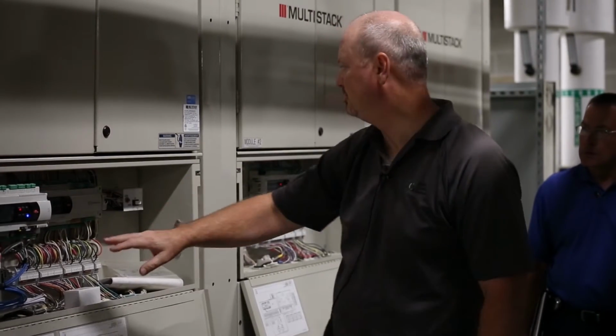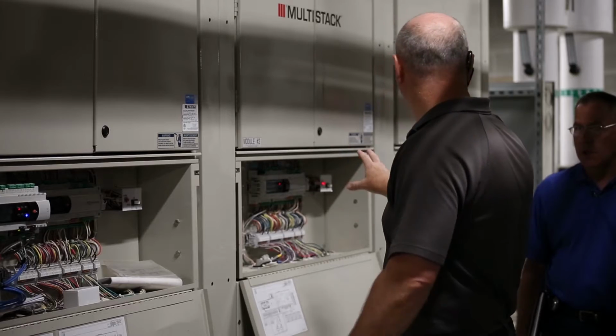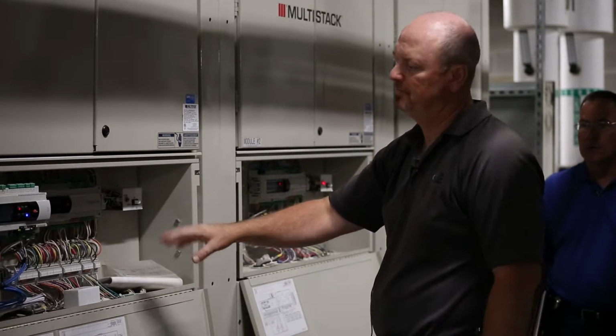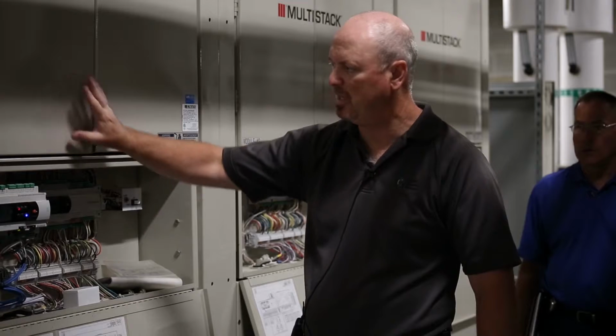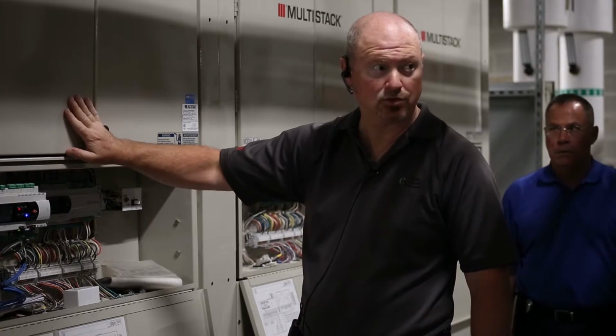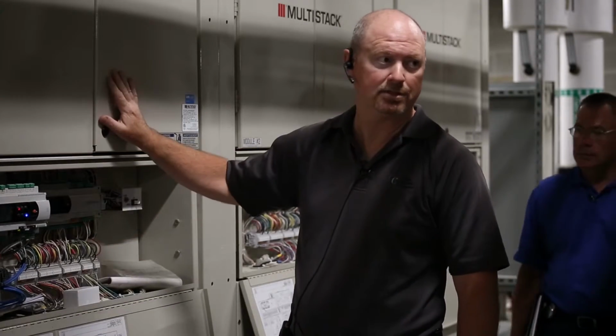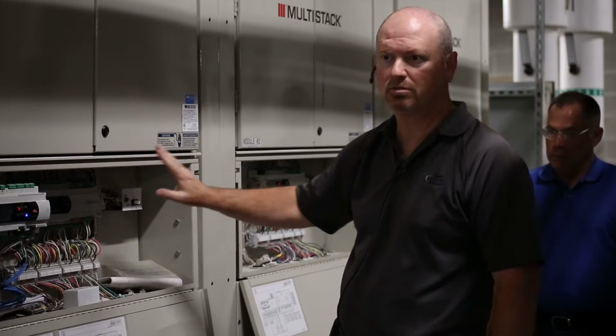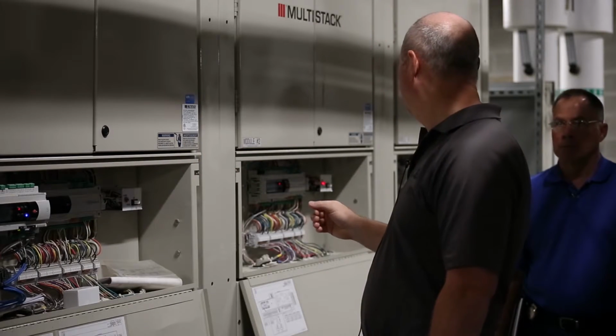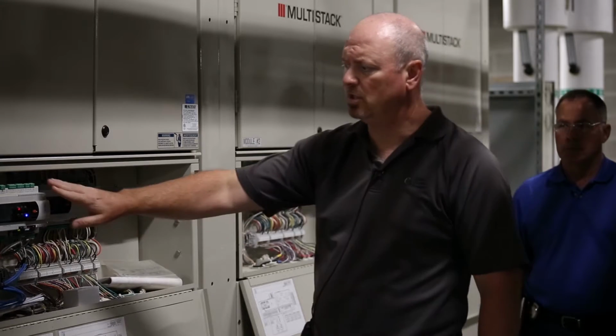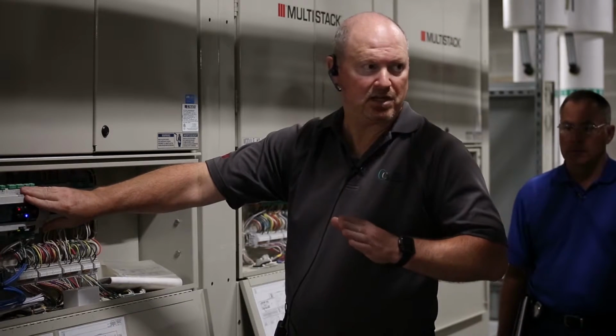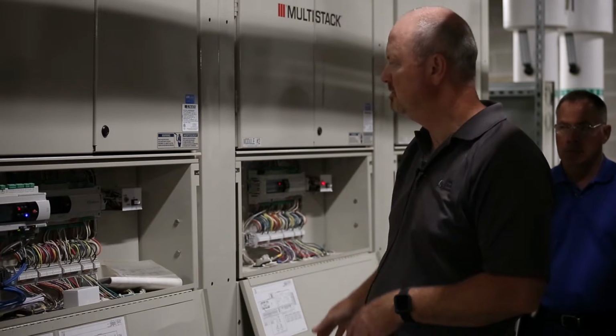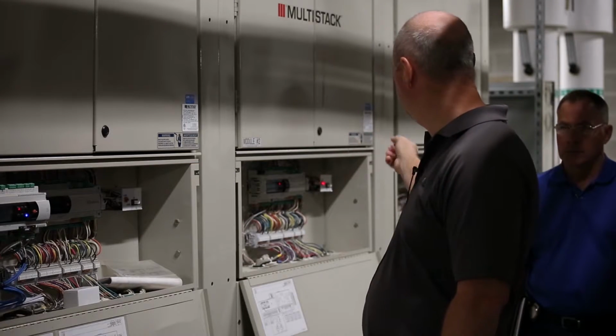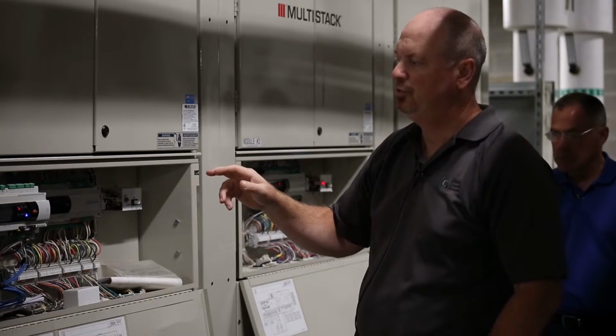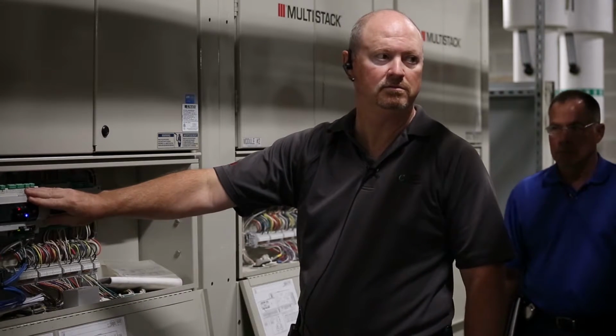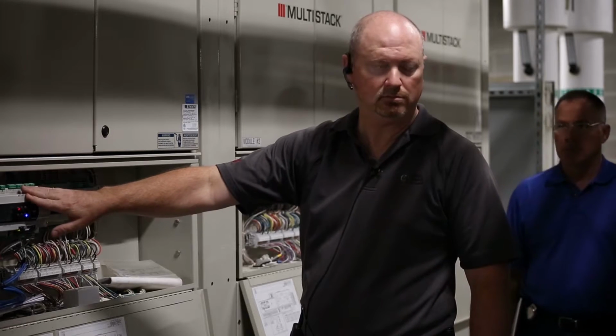This is your master, and these are all chiller module controllers. Obviously, this master is mounted on module 1, but it's not the actual controller of the compressors. This controls the compressors. This also gives alarms for everything. Even though you'll see an alarm on each module, you still have to reset it from the front end, which is the master.